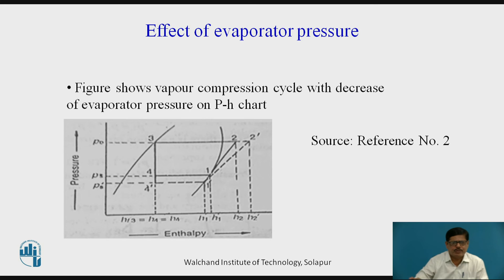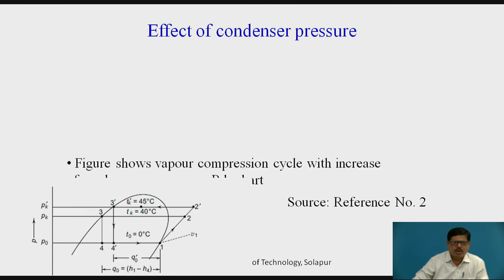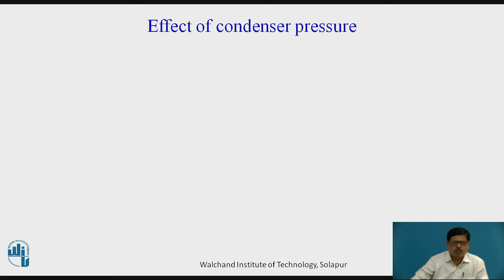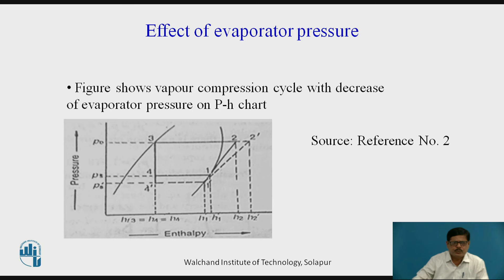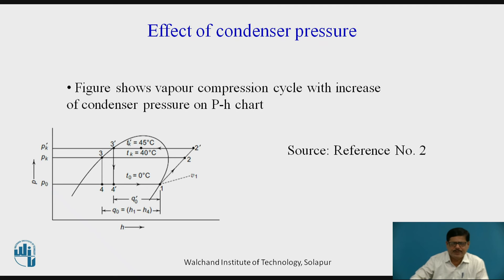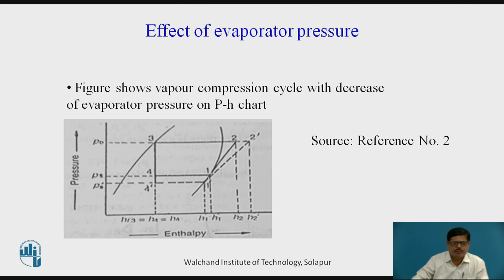Now let us see the effect of evaporator pressure. If the initial evaporator pressure is Ps and it decreases to Ps dash, then the simple vapor compression cycle is 1, 2, 3, 4, and with reduced evaporator pressure it will be 4 dash, 1 dash, 2 dash, 3, 4 dash. When the evaporator pressure decreases, the refrigerating effect will decrease, work of compression will increase, and therefore the COP of the cycle will always be reduced.